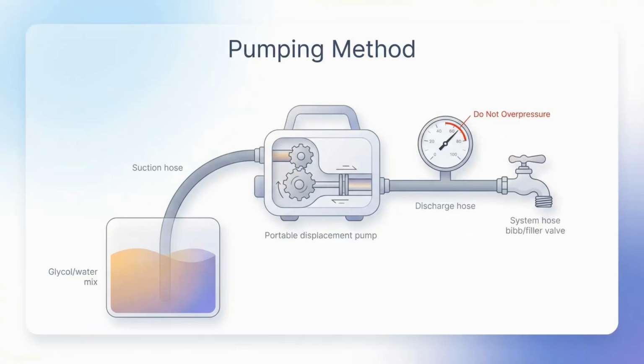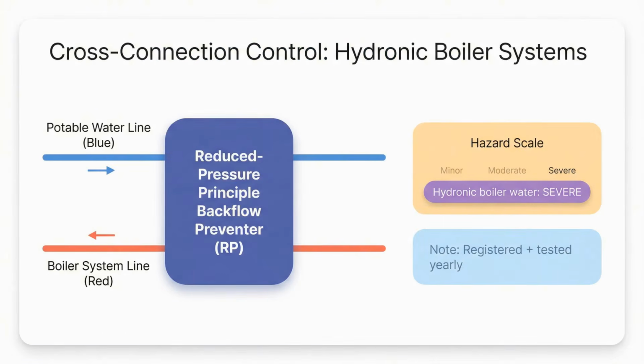The most common method is pumping a pre-mixed glycol water solution into the system. The pump's suction sits in the mix container, and the discharge connects to a filler valve or hose bib. As glycol is added, system pressure must be monitored to avoid overpressuring. If the glycol is in, but pressure is still low, the pressure-reducing station can be opened to top up to the correct setting. Cross-connection protection prevents non-potable boiler water from contaminating potable water. The authority having jurisdiction determines requirements, and standards commonly reference AWWA guidance. Hydronic water is treated as a severe hazard because of chemicals and additives, so a reduced pressure principle backflow preventer, an RP, is typically required, installed upstream of the pressure-reducing station, and it must be registered and tested yearly.